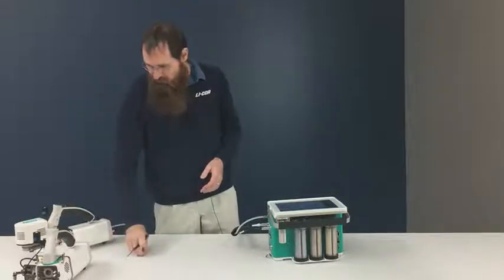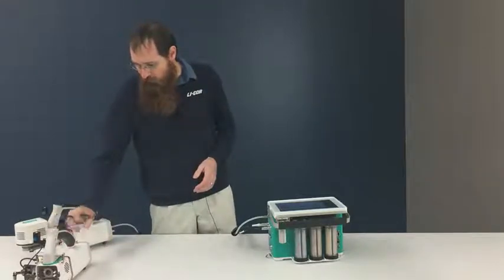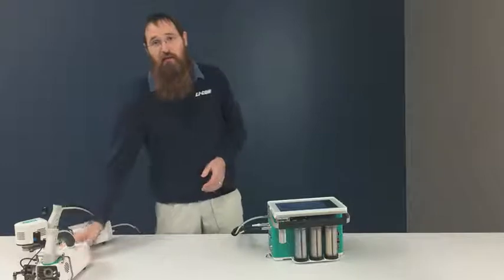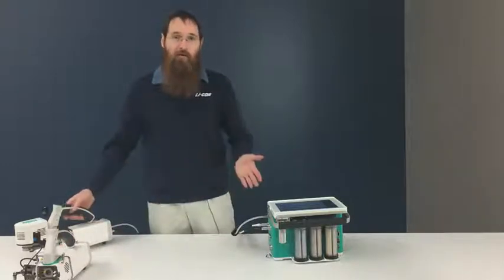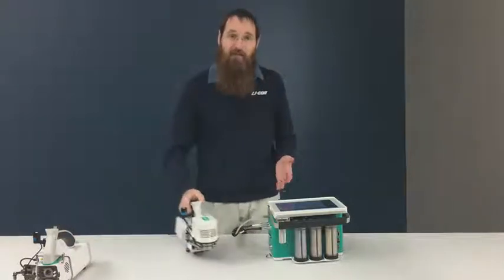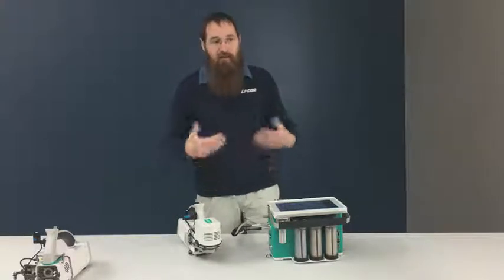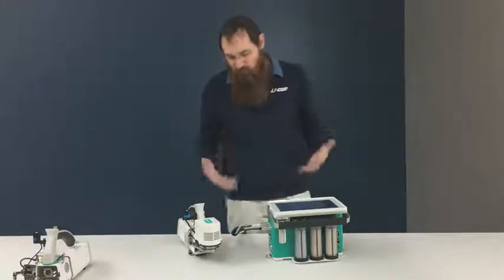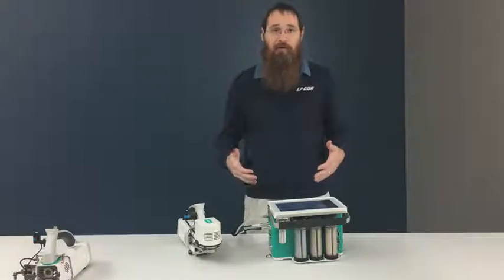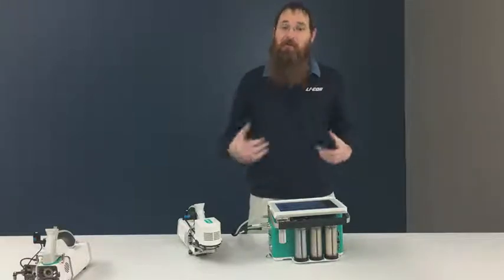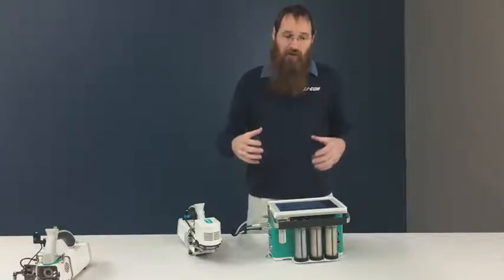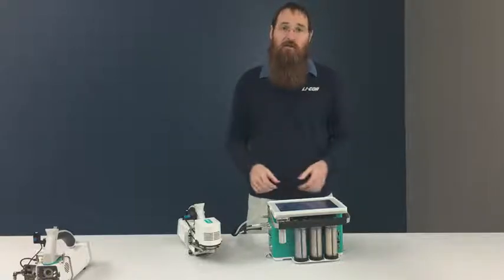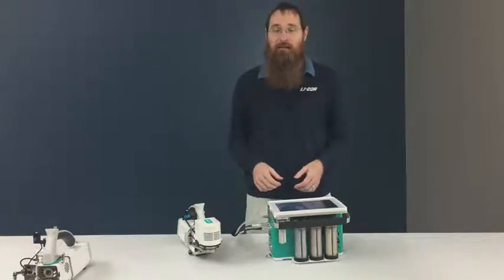If you've worked with the 6400 before, you'll often hear us call it a dumb instrument, because it doesn't know what's attached to it - it relies on the user to tell it. Using that same analogy, our 6800 is a smart instrument, because it knows what's plugged into it, and inherently knows what it needs to do and changes its software to use that device.